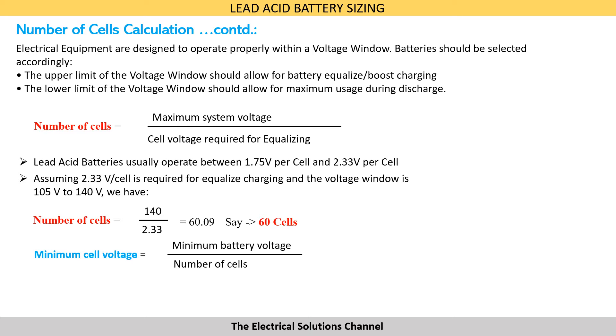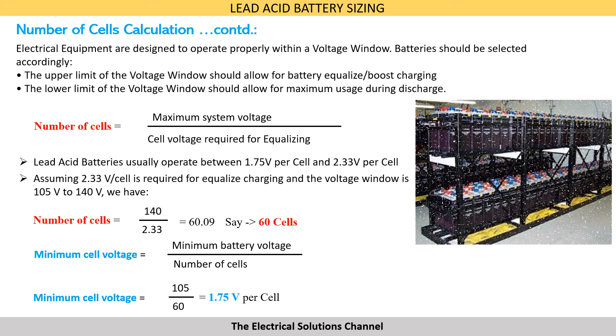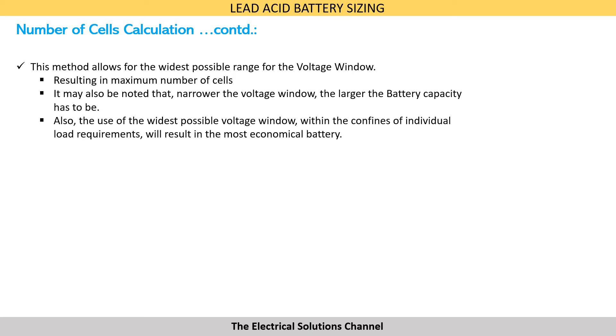Minimum cell voltage can be calculated as minimum battery voltage divided by number of cells. So minimum cell voltage in our case is 105 volts divided by 60 cells, which equals 1.75 volts per cell. The number of cells calculated by this method allows for the widest possible range of the voltage window.